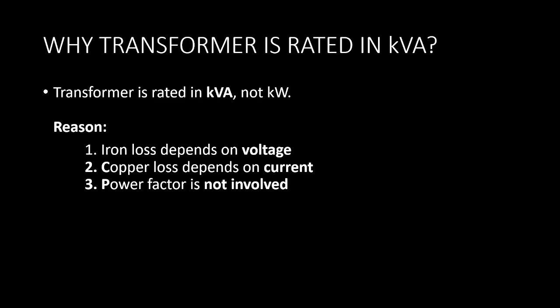Now let's discuss why transformer is rated in kVA. Transformer is rated in kVA and not in kilowatt, that is kW. Reason: point number one, the transformer core loss depends on the voltage. Point number two, the copper loss depends on the current, and the third point is power factor is not involved. So from here you can expect one question.